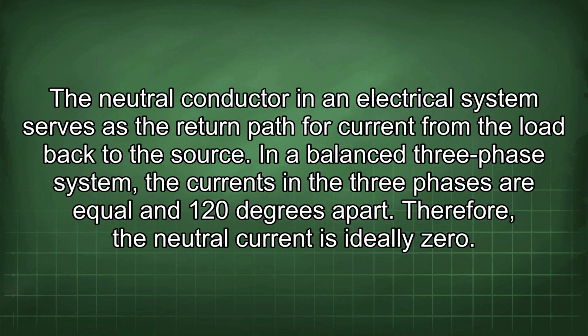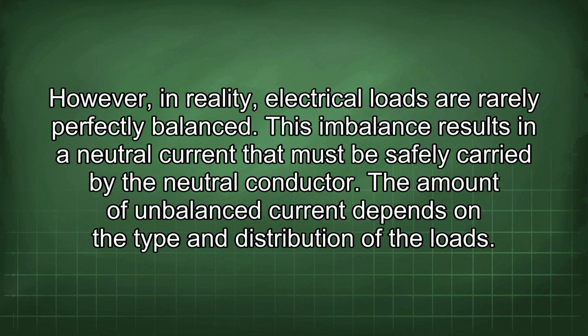The neutral conductor in an electrical system serves as the return path for current from the load back to the source. In a balanced three-phase system, the currents in the three phases are equal and 120 degrees apart. Therefore, the neutral current is ideally zero. However, in reality, electrical loads are rarely perfectly balanced. This imbalance results in a neutral current that must be safely carried by the neutral conductor.